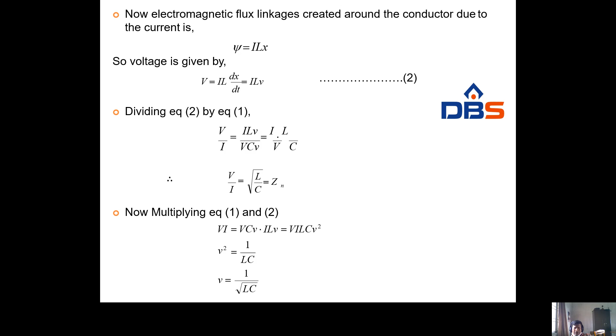Now for an overhead transmission line system, we know the L value. L is equal to 2 into 10 power minus 7 ln d by r Henry per meter, already derived in the first unit, inductance of a single line transmission system. And capacitance is 2 pi epsilon naught by ln d by r farad per meter. Now the velocity is 1 by root LC. L is 2 into 10 power minus 7 ln d by r, into C which is 2 pi epsilon naught by ln d by r. So ln d by r cancelled, leaving 2 into 10 power minus 7 into 2 pi epsilon naught. Substituting all these values, we get the velocity of the overhead transmission system, or velocity of the travelling wave, equal to 3 into 10 power 8 meters per second.